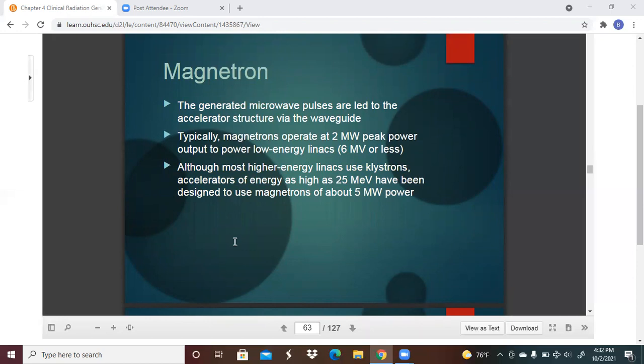So typically, magnetrons operate at 2 megawatts peak power output to power low energy Linacs, 6 MV or less. Although most higher energy Linacs use Klystrons, accelerators of energy as high as 25 MeV have been designed to use magnetrons of about 5 megawatts of power.